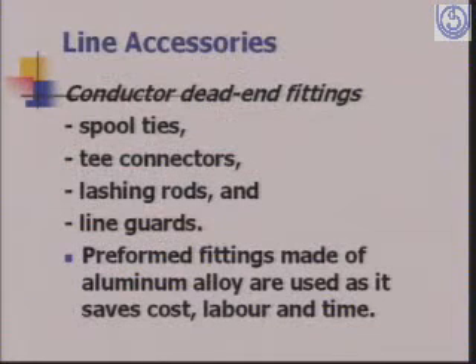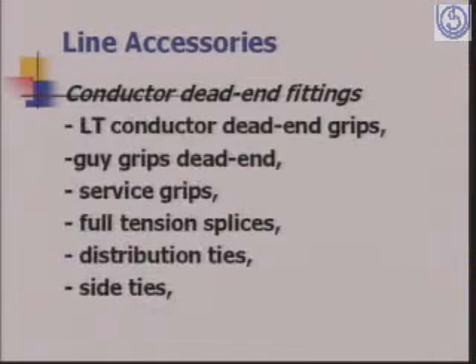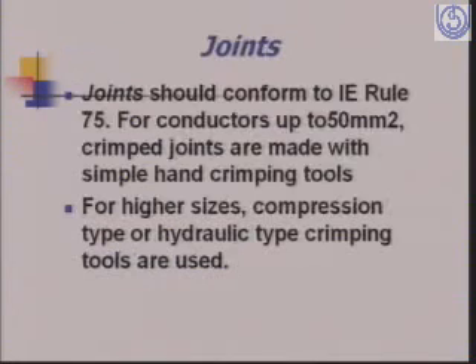The other line accessories which are used are spool ties, T-connectors, lashing rods and line guards and preformed fittings. There are other dead-end fittings like LT conductor dead-end grips, guy grips, service grips, full tension splices, distribution ties, side ties, which you all see when constructing a feeder or a line.